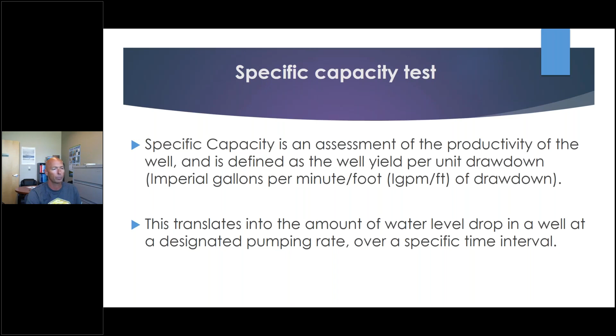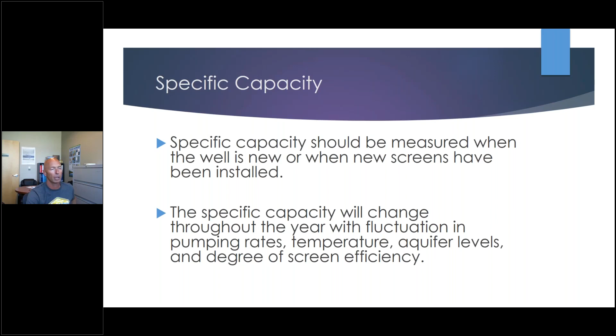Specific capacity should be measured when the well is new or when new screens have been installed. It's really tough to do specific capacity before the well screen is installed. We usually do it right after the screen has been installed in a new well, or during a pump test. The specific capacity will change throughout the year with fluctuations in pumping rates, temperature, aquifer levels, and degree of screen efficiency. And not for all wells. It can be in shallow wells, can be in deep wells. So every well can act different.